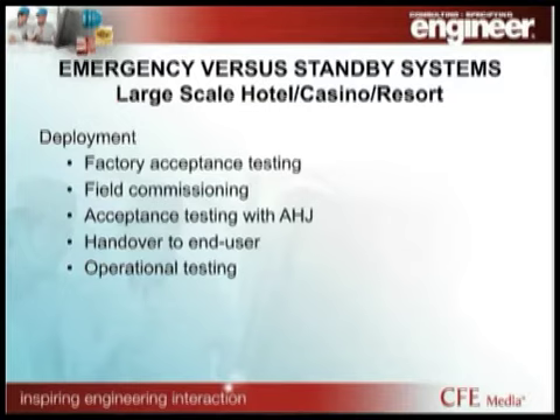Factory acceptance testing, when you're doing a parallel generation system, is a must, because what you really want to be doing is testing that equipment in a controlled environment at the plant and simulating all of the different control functionalities that are made up in your sequence of operation. And actually, what our firm does when we go to the factory acceptance testing is we try to break the gear. We try to make it do something that it shouldn't do, really kick the tires hard.